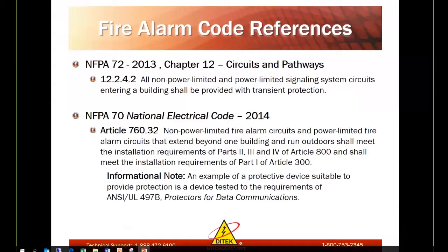NFPA 70 is the National Electrical Code, and Article 760.32 is a non-power limited fire alarm circuit and power limited fire alarm circuits that extend beyond one building and run outdoors shall meet the installation requirements of Parts 2, 3, and 4 of Article 800, and shall meet the installation requirements in Part 1 of Article 300. Informational note: an example of a protective device suitable to provide protection is a device tested to the requirements of ANSI UL 497B, which our devices are listed at, for protectors for data communications.